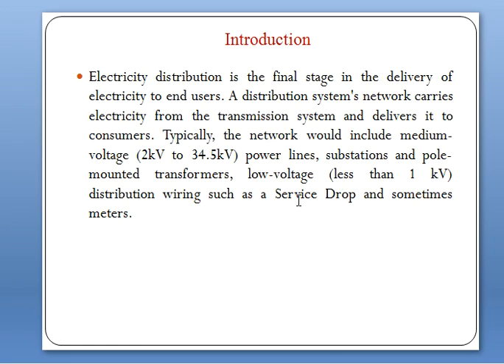These points of connection are normally open but allow various configurations by the operating utility by closing and opening switches. Operation of these switches may be by remote control from a control center or by a lineman. The benefit of the interconnected model is that in the event of a fault or required maintenance, a small area of the network can be isolated and the remainder kept on supply.